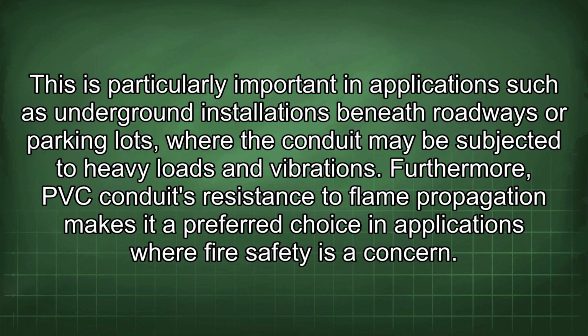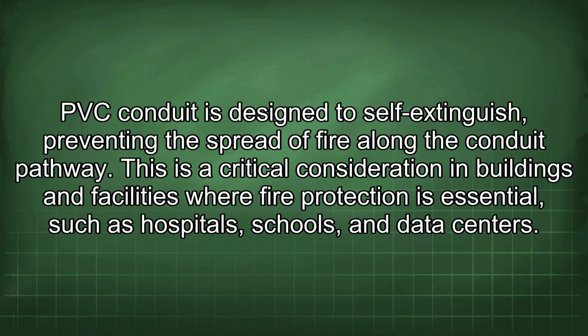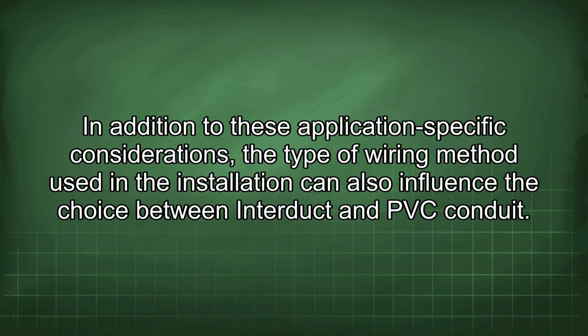Furthermore, PVC conduit's resistance to flame propagation makes it a preferred choice in applications where fire safety is a concern. PVC conduit is designed to self-extinguish, preventing the spread of fire along the conduit pathway. This is a critical consideration in buildings and facilities where fire protection is essential, such as hospitals, schools, and data centers. In addition to these application-specific considerations, the type of wiring method used in the installation can also influence the choice between Interduct and PVC conduit.